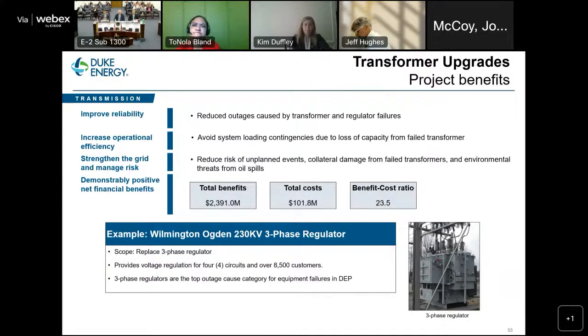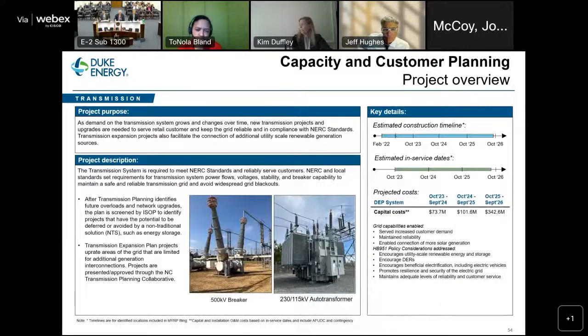The last thing I'll mention here is three-phase regulators are the top outage cause category for substation equipment failures in DEP for, again, outages emanating from the transmission system. When we look at substation equipment, we've had over 11 million customer minutes interrupted in the last 5 years. So it's very important for us to target these assets, upgrade these assets with designs that are less vulnerable to these failures. I'm going to move on to the last project area, which is our capacity and customer planning project area.